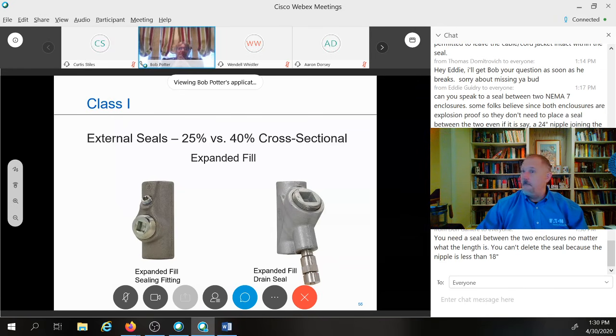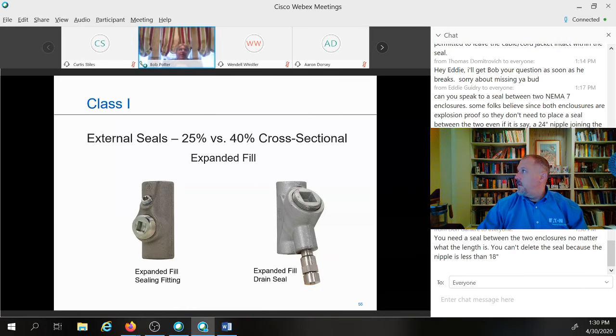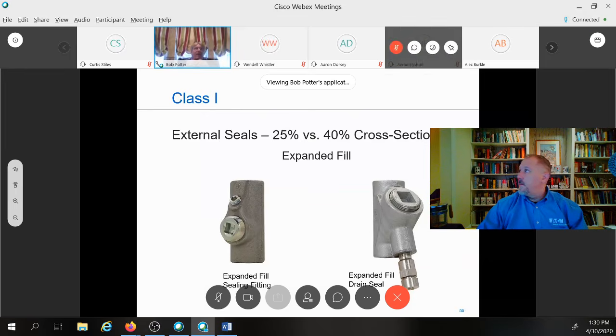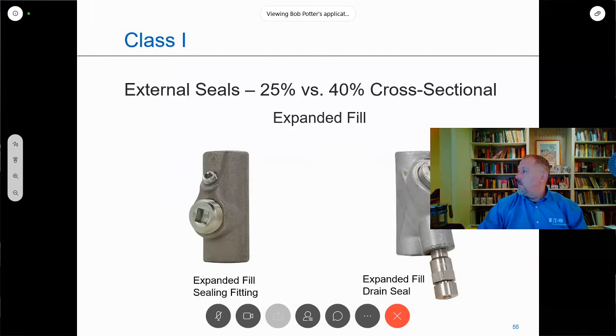I just saw a thing pop up saying you need a seal between two enclosures, no matter what the length, and that is not an accurate statement. In fact, within the National Electrical Code, they actually talk about if you have 36 inches or closer, you may put a seal in between them. So I just wanted to make sure that there wasn't some confusion there.